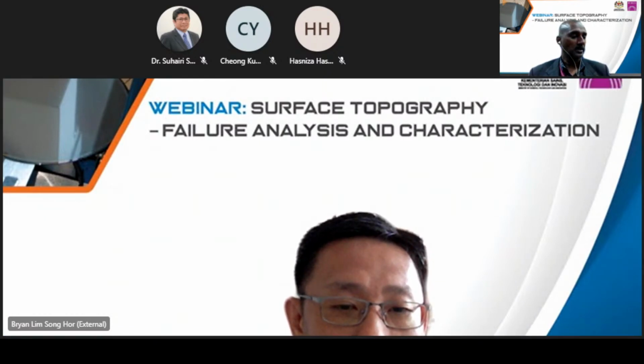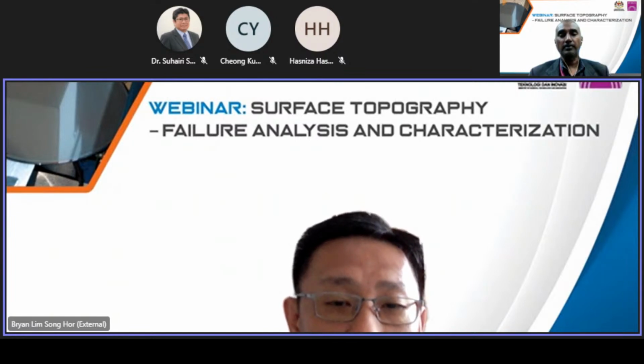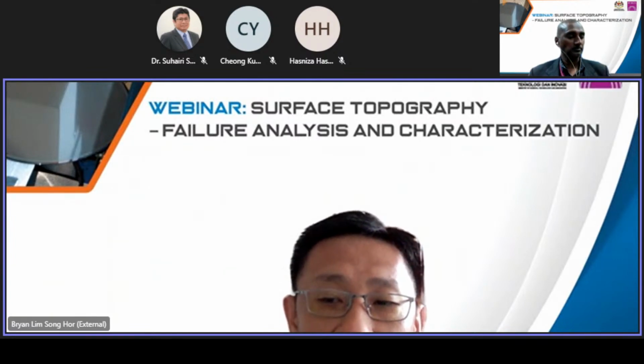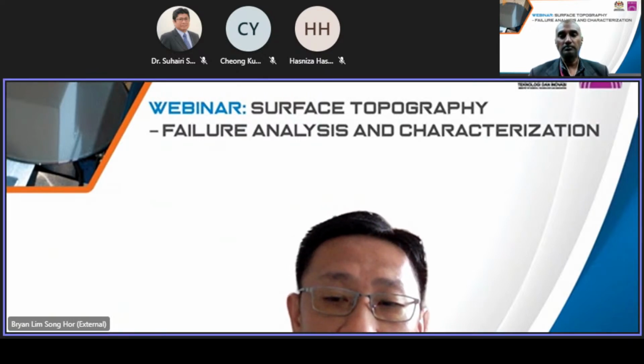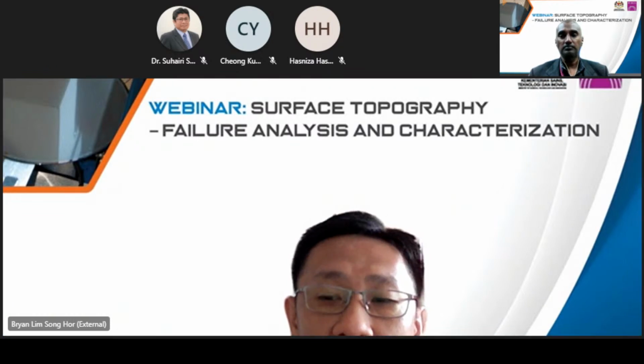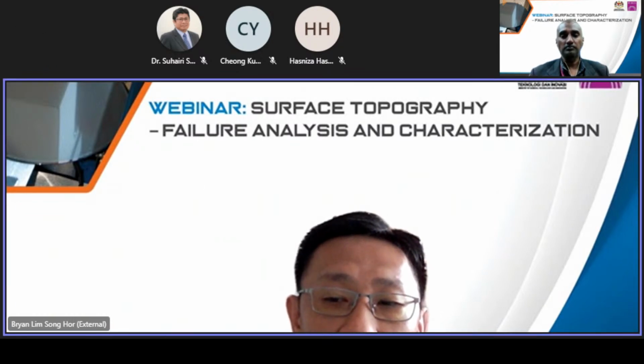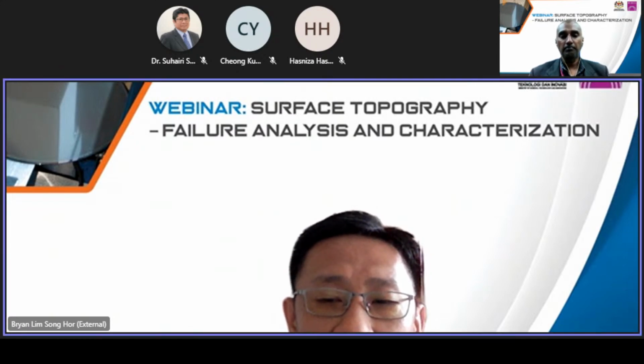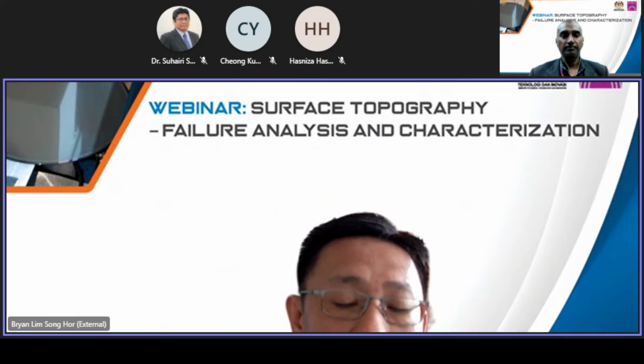Okay, we have another question. How do we know the tip of the cantilever is broken? All right, this is a good question. Usually we know the tip is gone when there are some abrupt changes in the measurement result or the image. For example, when you notice the image resolution is reduced and becomes blurry or not clear, or has some repeated pattern on the image, this is the result of tip wear. So if you see big changes in the image, most of the time the tip is worn out.